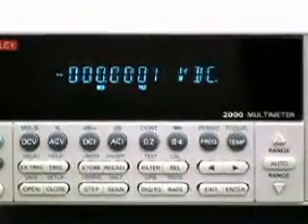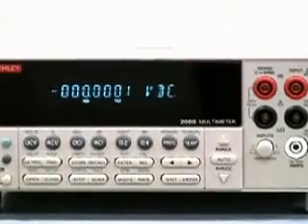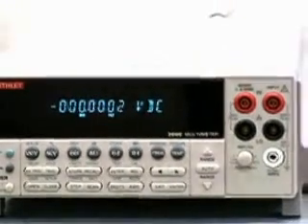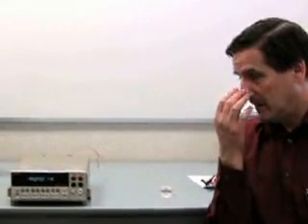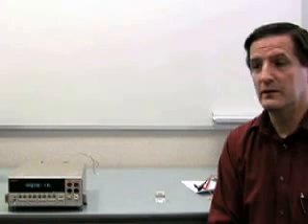Standard on the model 2000 for communication is GPIB or IEEE 488 and RS-232. That's right, two instrument interfaces in one box. So if you happen to have a standard RS-232 port, you plug right in, or you use a standard GPIB port, which requires an interface in your computer. It runs on standard commands for programmable instruments, known in the industry as SCPI. Another unique feature is the 34401 emulation mode. All that means is if you have another box from Agilent, the model 34401, you put it in this emulation mode and you do not have to have any programming changes. Saves you time and money.